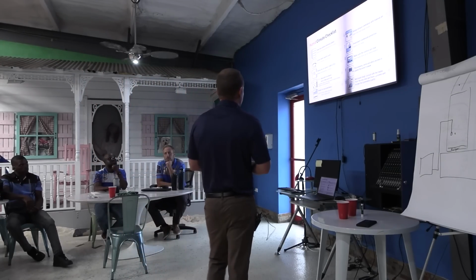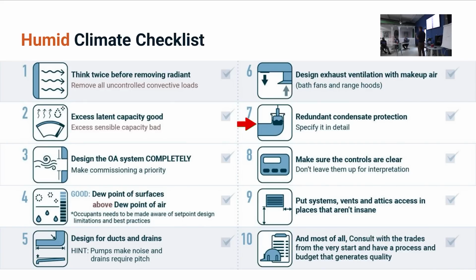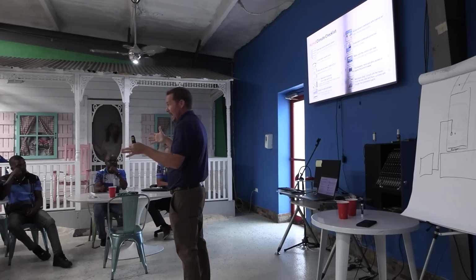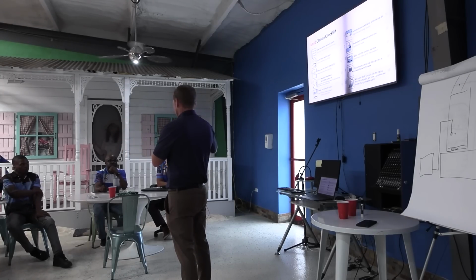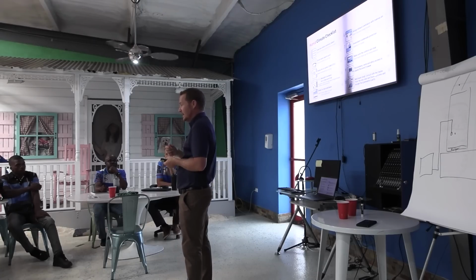It's balancing it there. Redundant condensate protection—we've covered that plenty. Make sure the controls are really clear, which means if you're selling dehumidifiers or complicated communicating systems, make sure the installers are really clear on what is expected in the setup. It's not just a matter of plop it in and walk away. What do we leave it set at when we leave? How do we duct it in? All those things have to be designed.